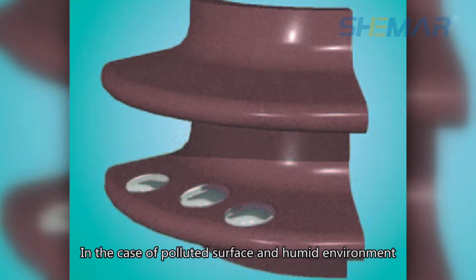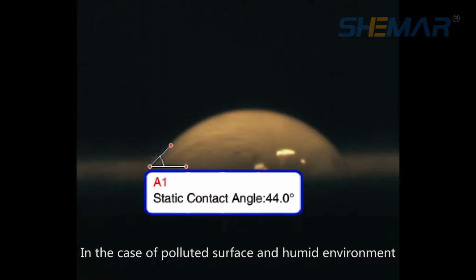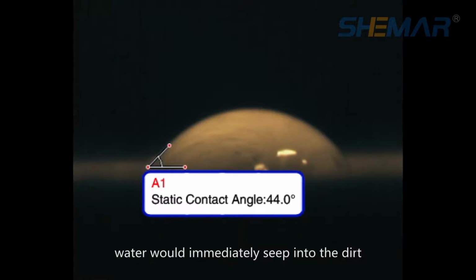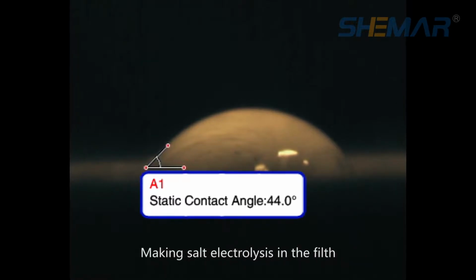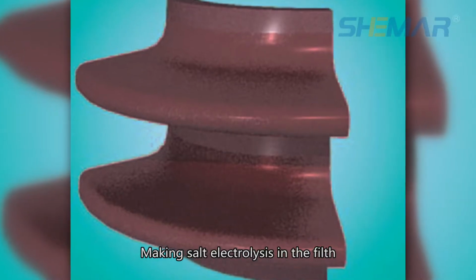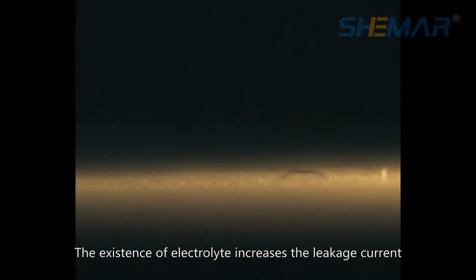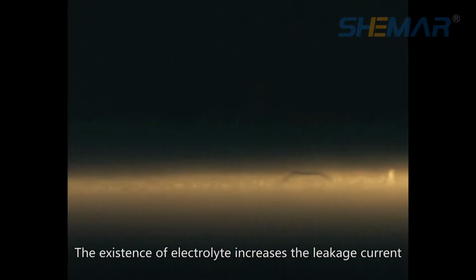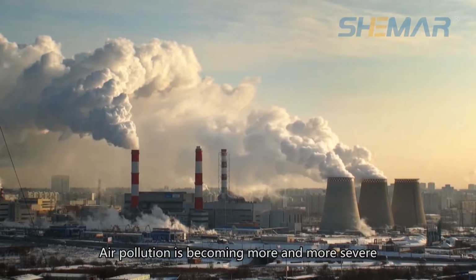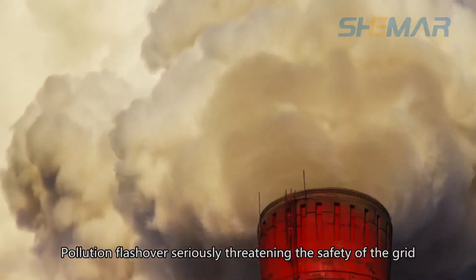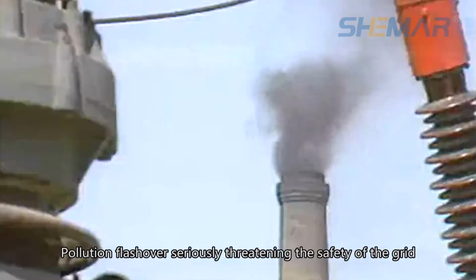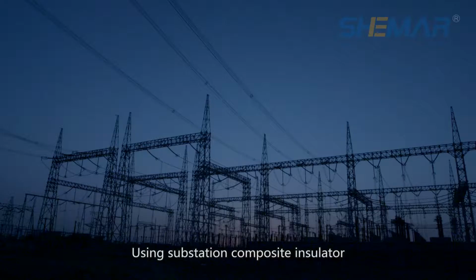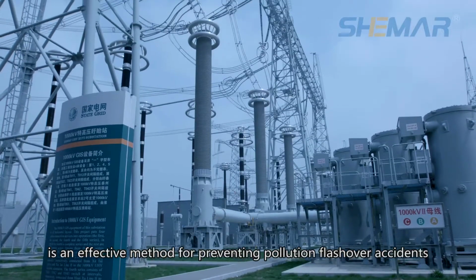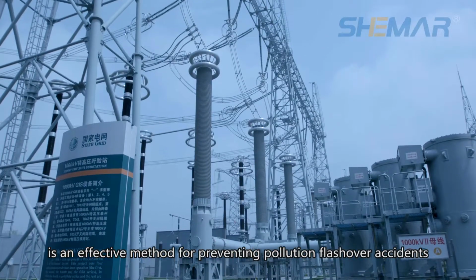In the case of a polluted surface and humid environment, water seeps into the dirt, causing salt electrolysis in the filth. The existence of electrolytes increases leakage current, causing pollution flashover. As air pollution becomes more severe, pollution flashover seriously threatens grid safety. Using substation composite insulators is an effective method for preventing these accidents.